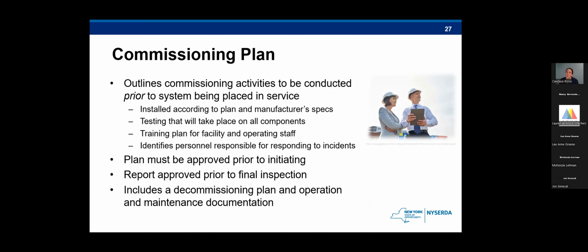So here we have the commissioning plan requirements that are necessary via the code. Commissioning needs to take place to ensure that the system will perform as intended, and is required to occur prior to the project being placed into service. Specifically, the commissioning plan itself needs to include a narrative description of the activities that will be accomplished during each phase of commissioning, including the personnel intended to accomplish each of the activities. You need to provide a listing of the specific energy storage system and components, controls, and safety related devices to be tested, and a description of the tests to be performed and functions to be tested.